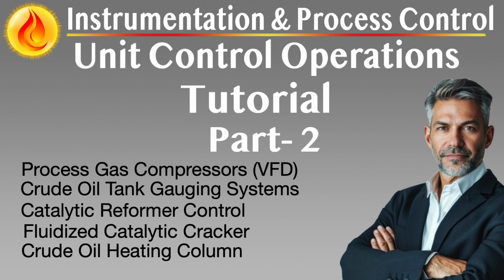Safety and reliability are managed via tight integration with safety instrumented systems, SIS, and emergency shutdown systems, ESD. Overpressure, high level, and tray flooding detection are implemented with automated protective actions, such as flash gas diversion, heater ramp down, or reflux cutback. Alarm management systems provide operators with prioritized guidance during disturbances, and smart valve diagnostics ensure that control elements respond correctly during transient conditions.